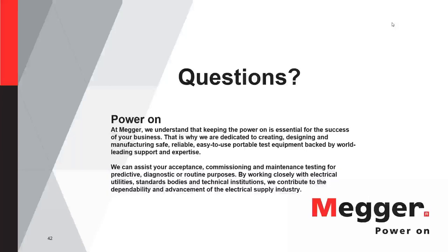All right, Robert, I'm throwing one at you. This comes from Jimmy. Jimmy asks, what system or product do you have for online partial discharge testing? For online partial discharge testing, we have one product that is called the UHF PDD, but this is mainly tailored on the substation side, say PD on terminations, switchgear, and not so much on the PD measurement on cables, because a proper PD test or PD diagnostics on cables should be done as an offline test.